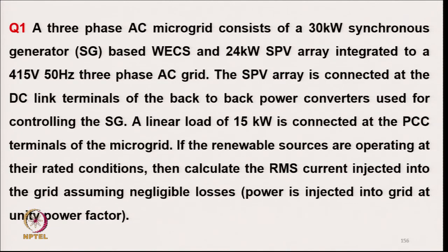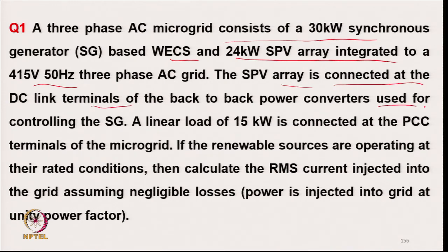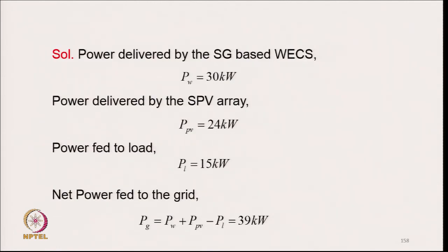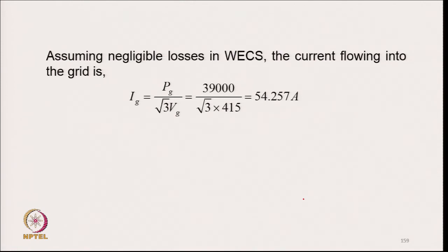Numerical Problem 1: A three-phase AC microgrid consists of a 30 kW synchronous generator based wind power energy converter and a 24 kW solar PV array, both connected to a 415 V, 50 Hz three-phase AC grid. A linear load of 15 kW is connected at the PCC terminal. If renewable sources are operating at rated condition, calculate the RMS current injected into the grid assuming negligible losses and unity power factor. Net power to the grid is 30 + 24 − 15 = 39 kW, giving a grid current of 54.257 A.